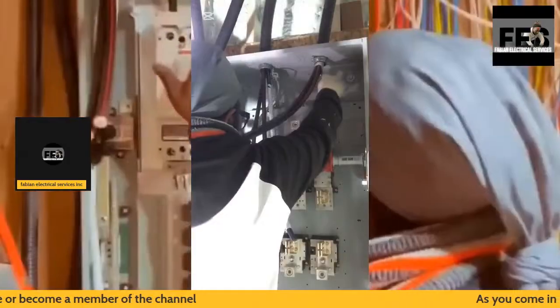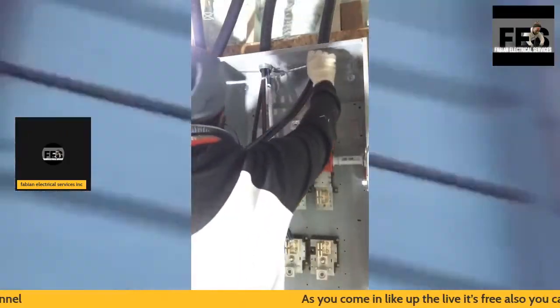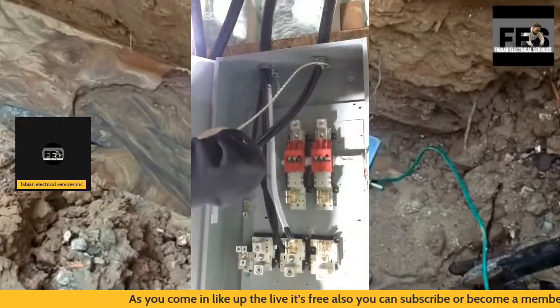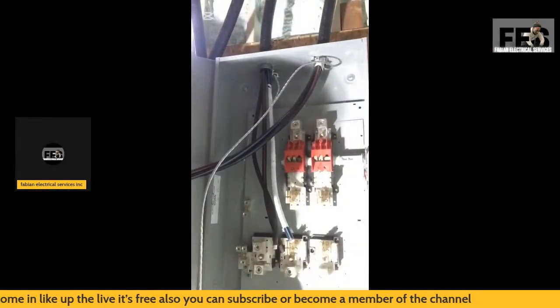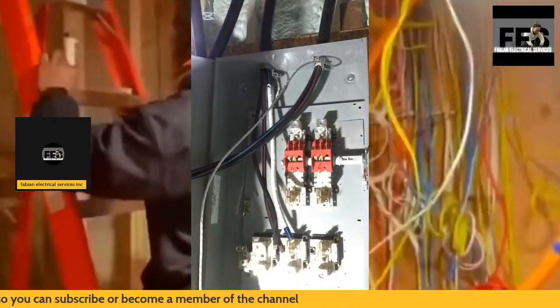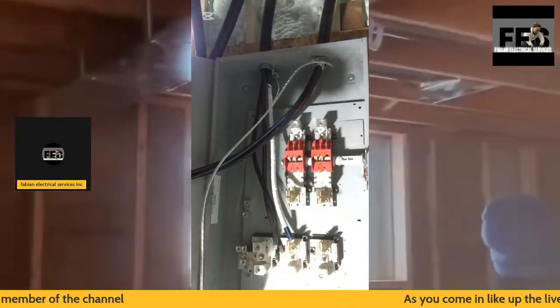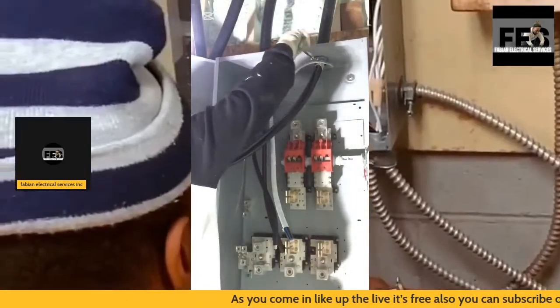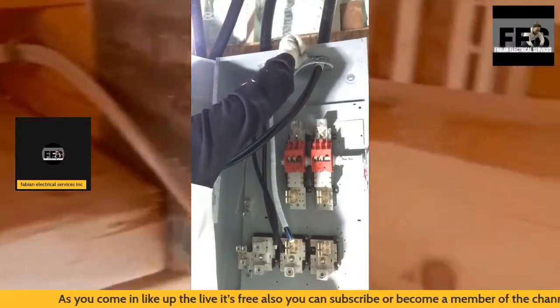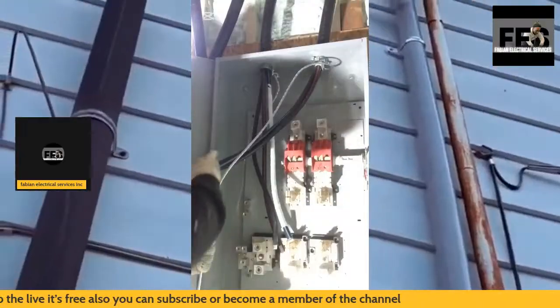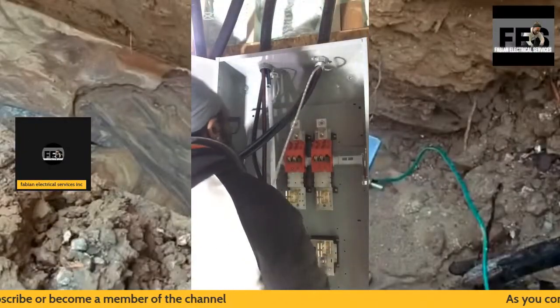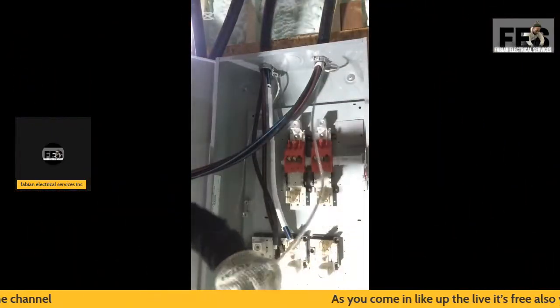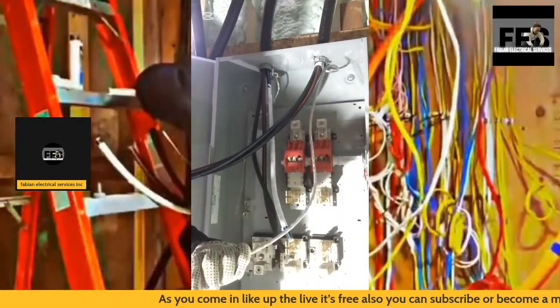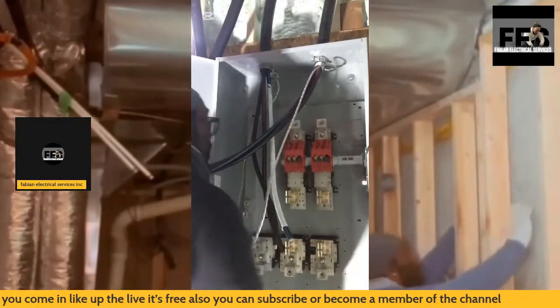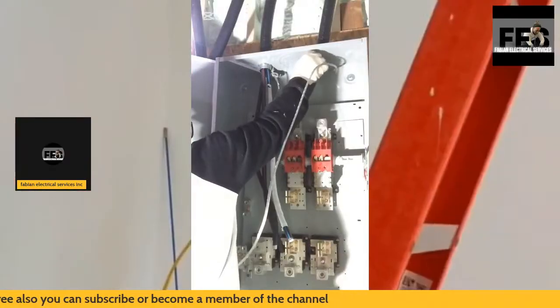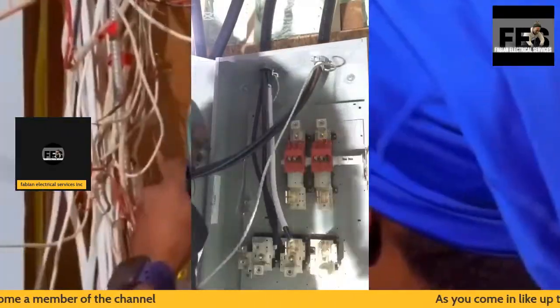So as you can see, the reason why I said I like to keep the white paper on is it simply helps with the cable. As you can see, the cable is locked in place. Once you disassemble that, it gives you a lot more problems getting the cable inside of the connector. So that's why I always make sure I land my cables inside of the disconnect, inside of the connectors, and then I remove that. Then I go ahead and simply ground off my ground. I do my groundings. So this is a grounding and bonding installation. There are two different things when it comes to bonding and grounding. They serve two different applications, so never get that confused.